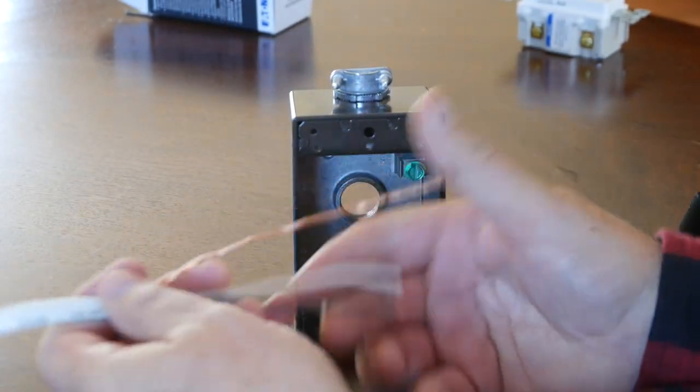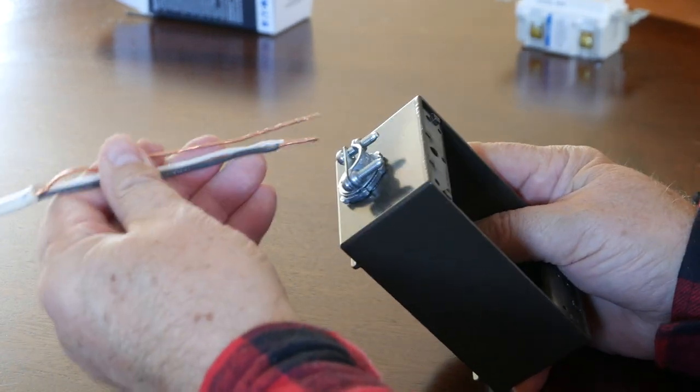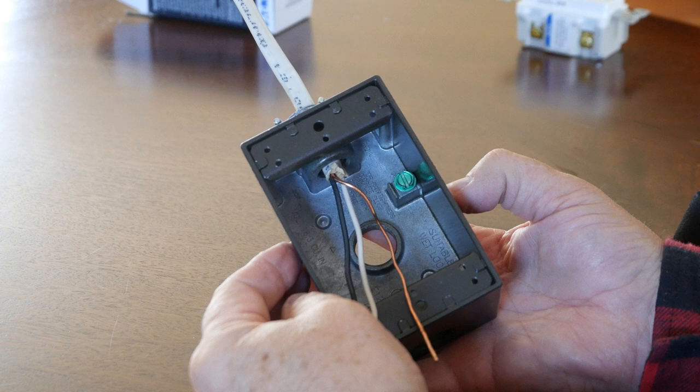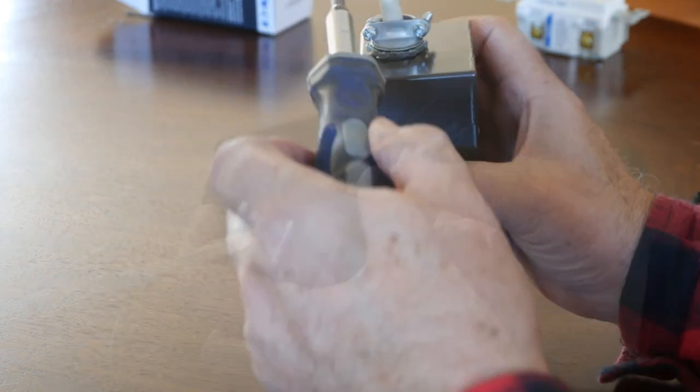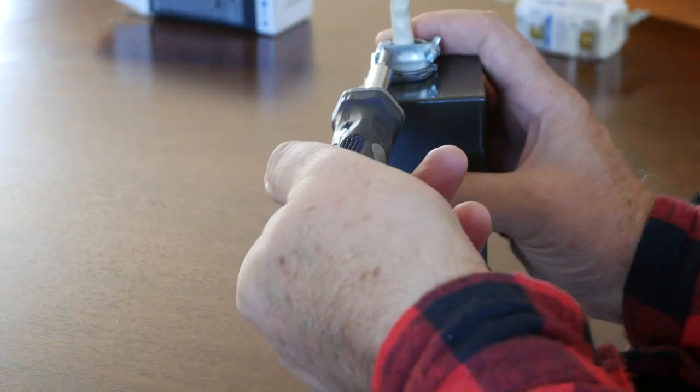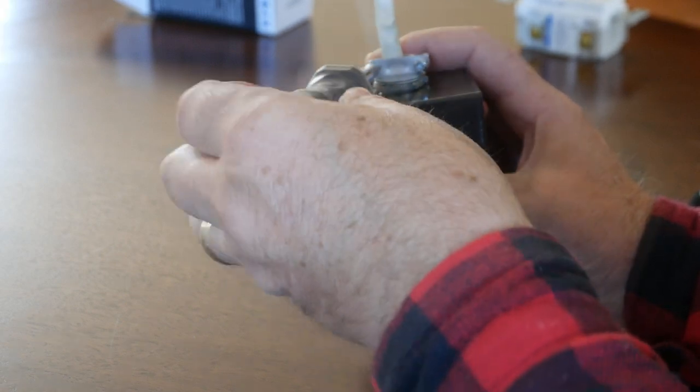Next, I'll show you in advance how we performed the wiring while the box is here on the tabletop with good lighting. I stripped off about six inches of the outer sheathing on this pretend bundle of wires and routed it down through the cable clamp opening. Allow a small amount of the sheathing to pass inside the box. Turn the clamp whereby you can reach the screws from the side then tighten both screws against the wiring bundle sheathing.